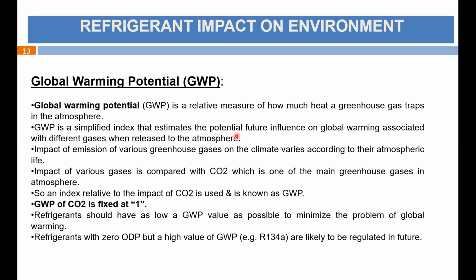So this global warming potential is a simple index. This is a comparative measure. The global warming potential of CO2, which is the most prominent greenhouse gas, is considered as 1. So compared to CO2, what is the index of the other gas? What is the potential of the other gas for global warming? This is measured in terms of GWP. So a refrigerant should have as low a GWP value as possible to minimize the problem of global warming.